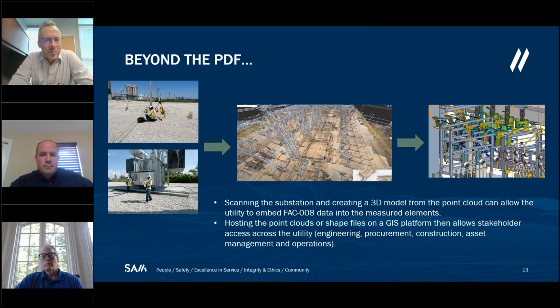Where a point cloud, a scanned file of your substation, becomes very useful is when you need to replace a piece of equipment inside the substation to avoid derating the line. Going back to the most limiting series element, if you have a disconnect switch that's rated less than your conductor, you need a project to replace that switch.